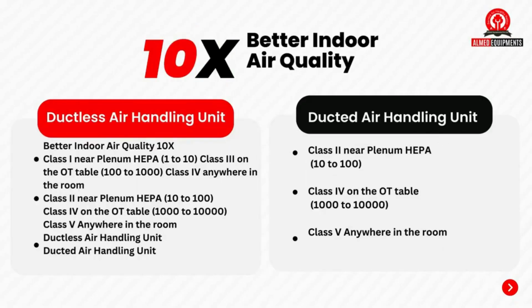10 times better indoor air quality is provided by the ductless air handling unit. Class 1 near the plenum HEPA, Class 3 on the OT table, and Class 4 anywhere in the room is provided. Whereas in the ducted air handling unit, Class 2 near the plenum HEPA, Class 4 on the OT table and Class 5 anywhere in the room is being provided.